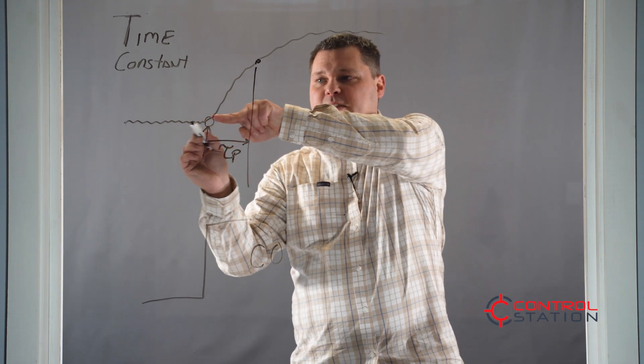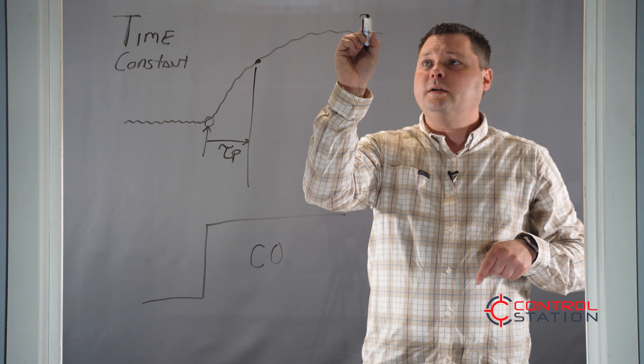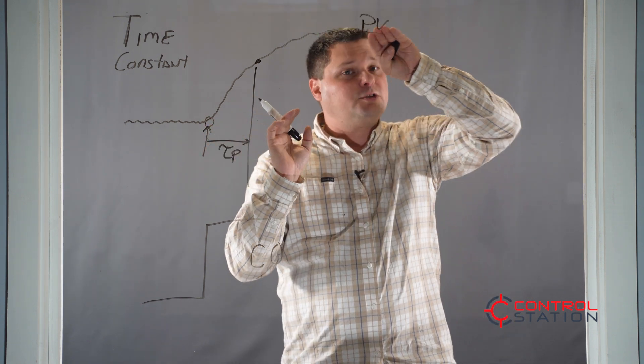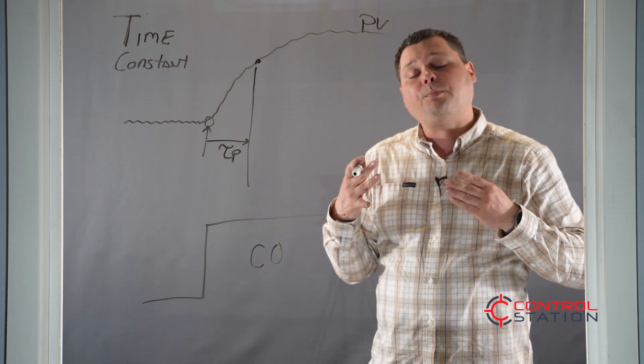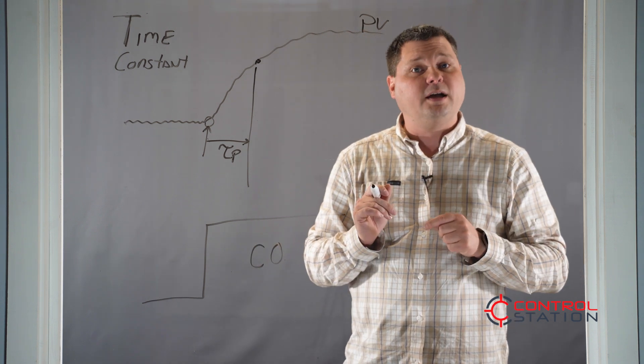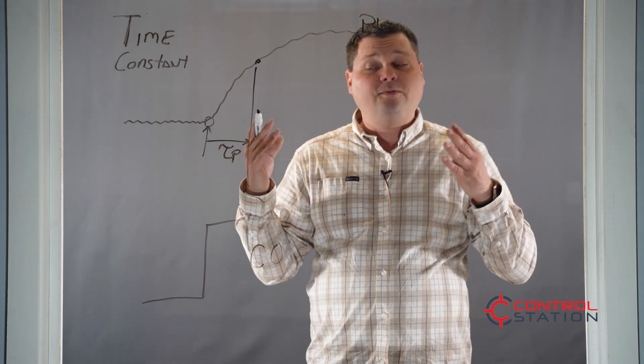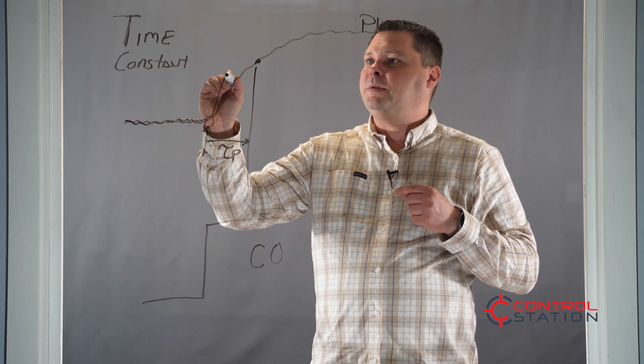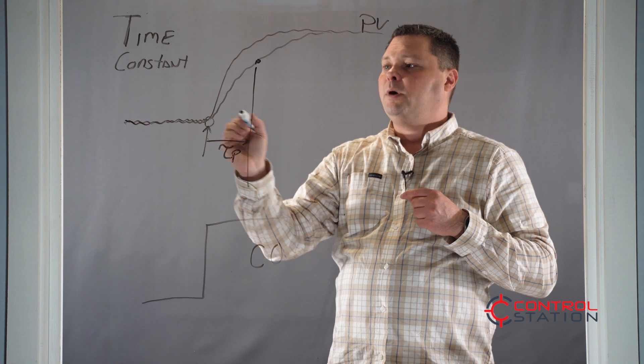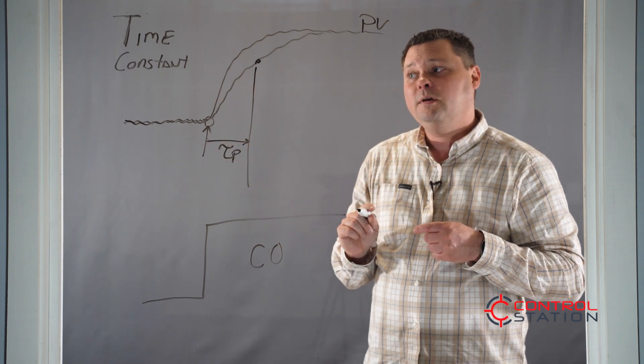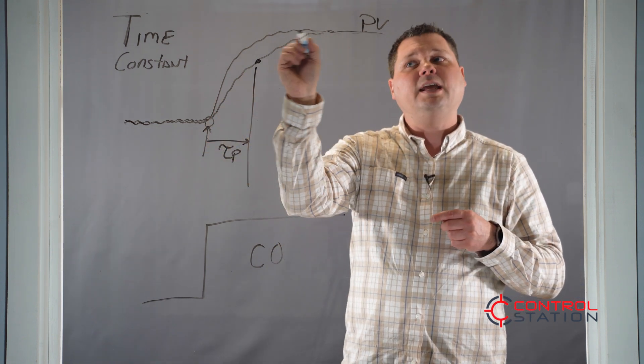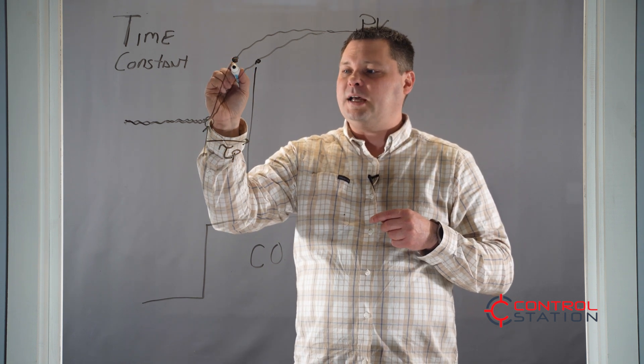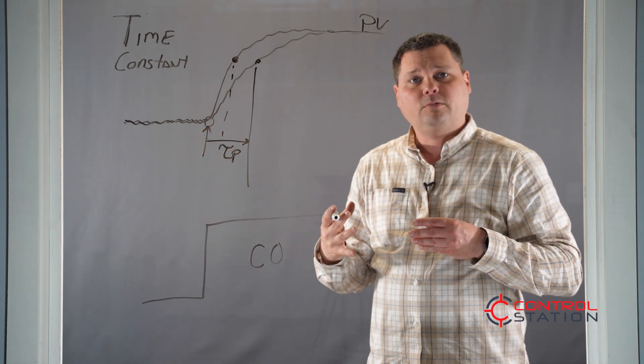So if this is our process variable, how fast does it get there? How fast does it start to respond? If I were to tell you that the process had a small time constant, that would mean it's very fast. A process with a small time constant may look something like this, where it moves very quickly. Fast moving loops are still going to end at the same point, but it's actually going to reach that 63% of the way there faster.